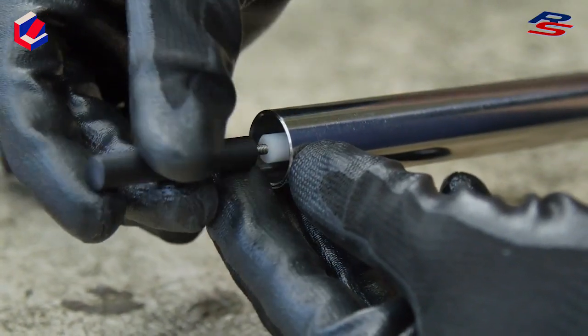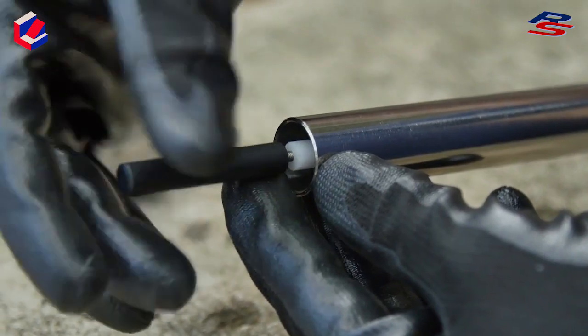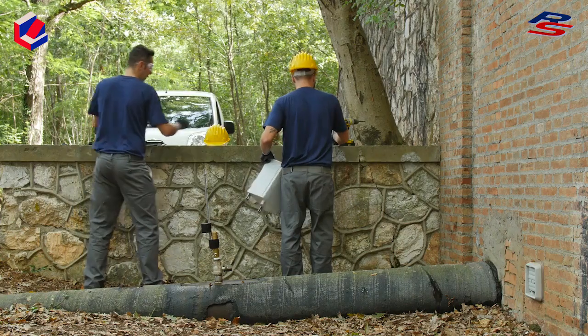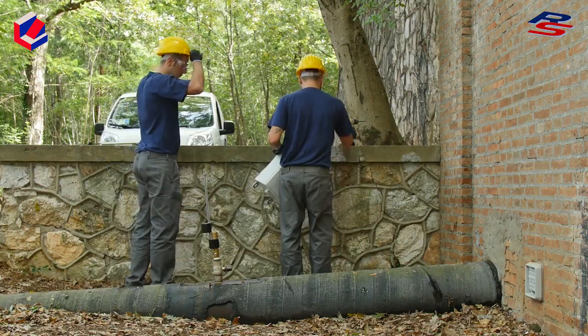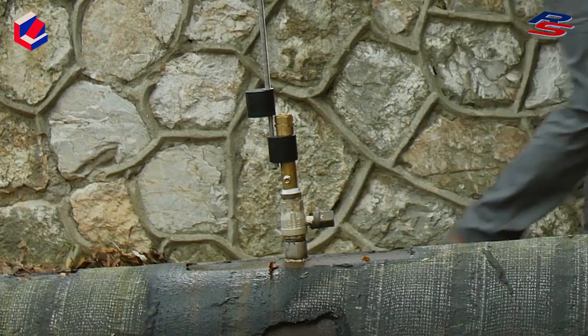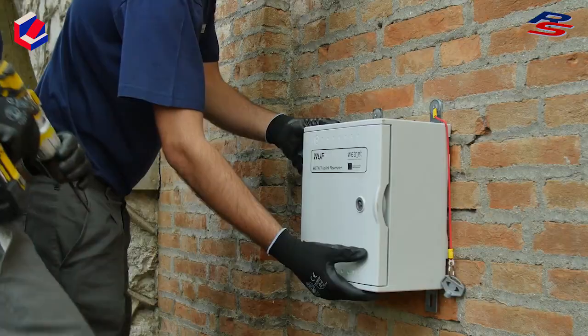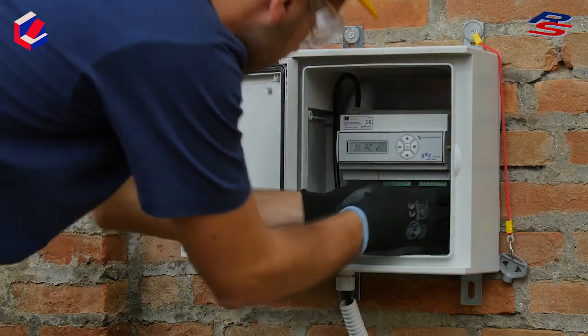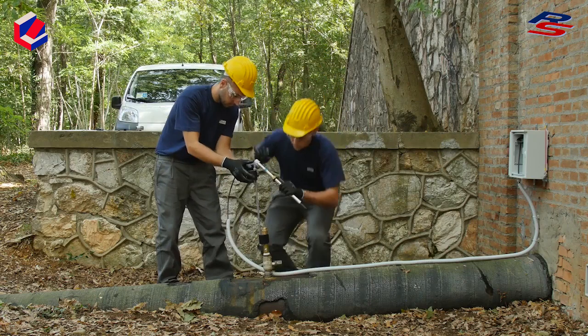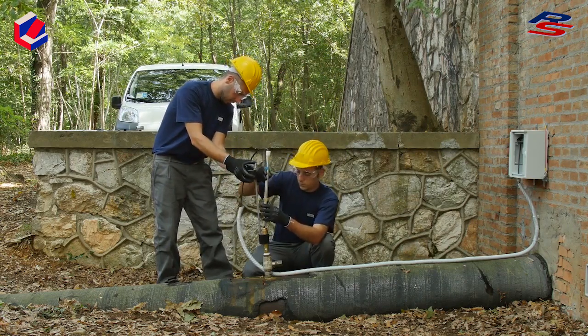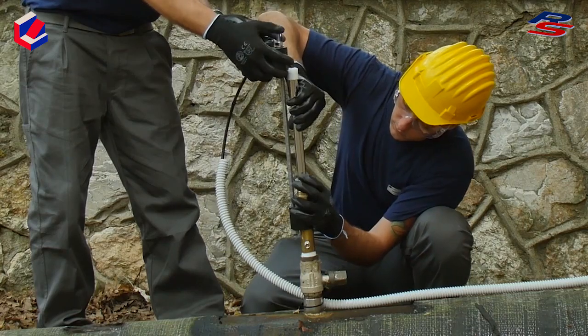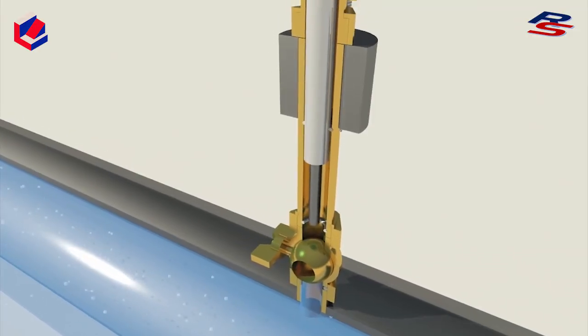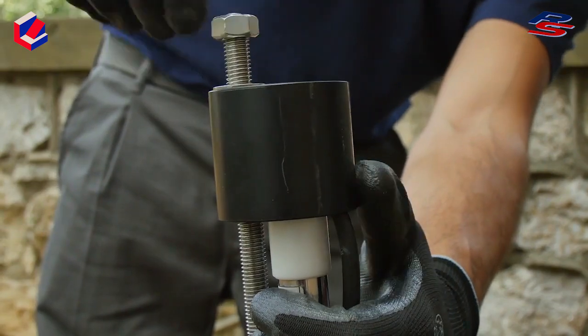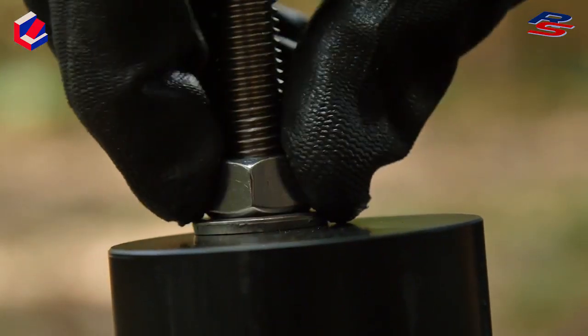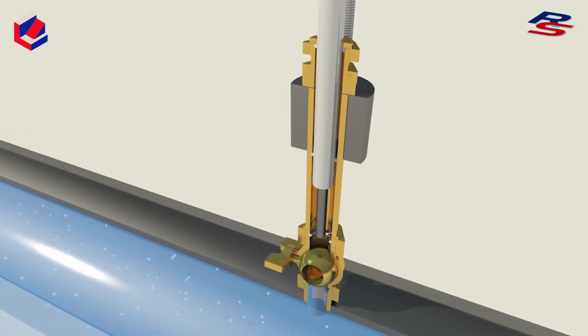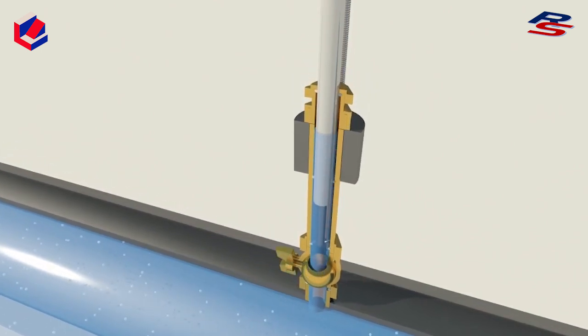The Resotech flow sensor has been designed for flexibility, incremental deployment, scalability, coexistence and/or integration with existing measurement and control systems, including communication infrastructures. To insert the sensor in the pipeline, the lock ring on the inserter is loosened, and the metering device is inserted to the position in which the seal is guaranteed. The valve is opened and then closed again after letting the water enter the inserter chamber.